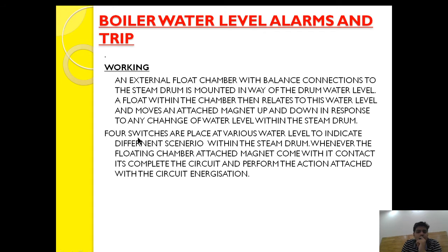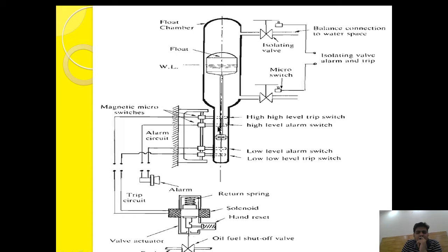Four switches are placed at various water levels to indicate different scenarios within the steam drum. When the float chamber's attached magnet comes in contact with a switch, it completes the circuit and performs the action attached to that circuit. When the magnet moves up or down and reaches a switch position, it completes that circuit and initiates an alarm or trip depending on the level.